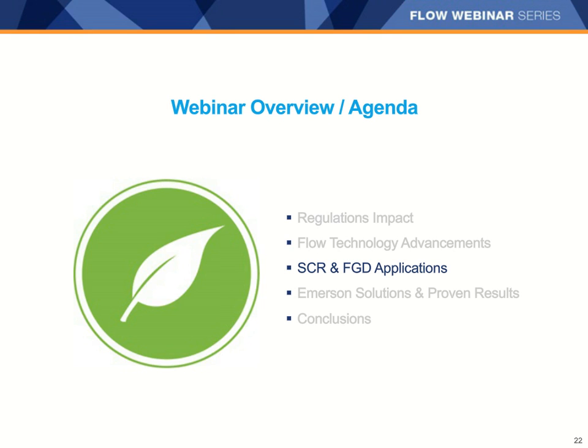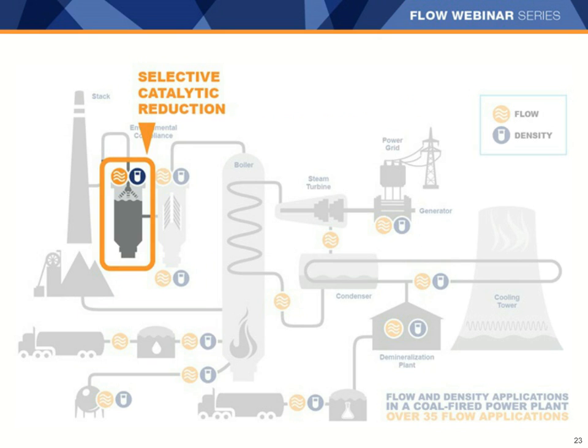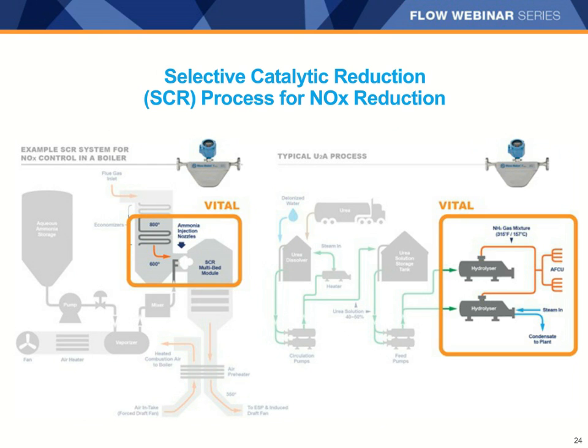Let's look closer now at the selective catalytic reduction and flue gas desulfurization applications. First, I'd like to highlight the selective catalytic reduction process and its conversion of nitrogen oxide compounds. Selective catalytic reduction is a means of converting nitrogen oxides, also referred to as NOx, with the aid of a catalyst into diatomic nitrogen and water. A gaseous reductant, typically anhydrous or aqueous ammonia or urea, is added to a stream of flue gas and is absorbed into a catalyst. Some of the challenges facing users of SCR technology are making sure that the ratio of reductant to catalyst is correct, and the amount of flue gas being scrubbed.